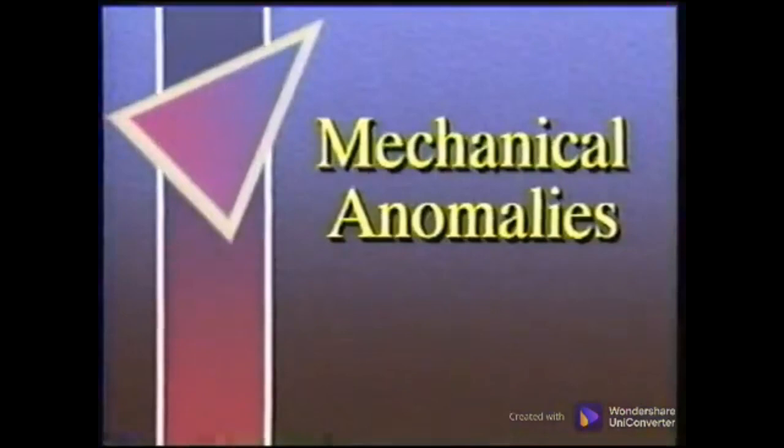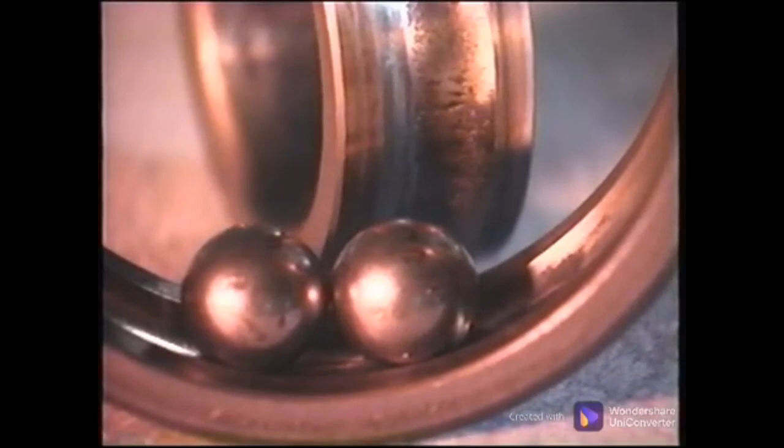Some mechanical problems can be clearly seen with a thermal image. When a bearing degrades or there is inadequate lubrication, the friction generates heat, which can show up as a hot area at the bearing housing or bearing mounting location. Remember that for most oil-lubricated bearings, the oil breaks down at 160 degrees Fahrenheit. Bearings that are in this range are too hot. Misalignment is a fault that is easily recognizable using thermal imaging. The easiest place to spot misalignment is at the coupling.